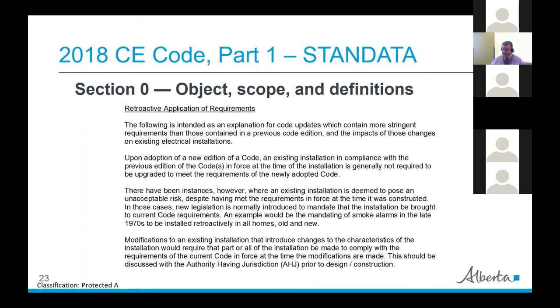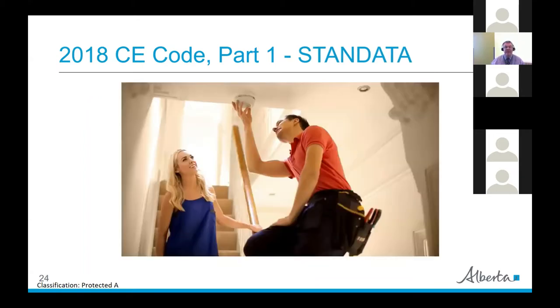There's a nice piece on that with an example of an electrician working on a smoke alarm in what appears to be an older home. Modifications to an existing installation that introduce changes to the characteristics of the installation would require that part or all of it be made to comply with the requirements of the current code in force at the time the modifications are made. Those are the kinds of things SCOs have to deal with in the field.